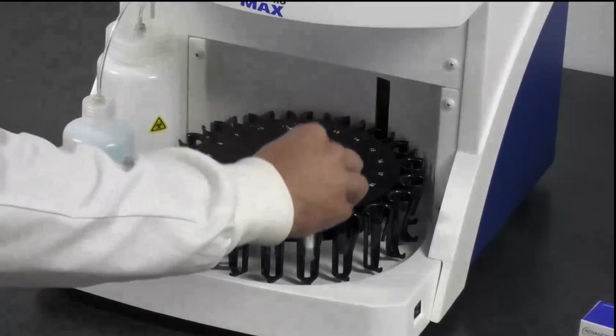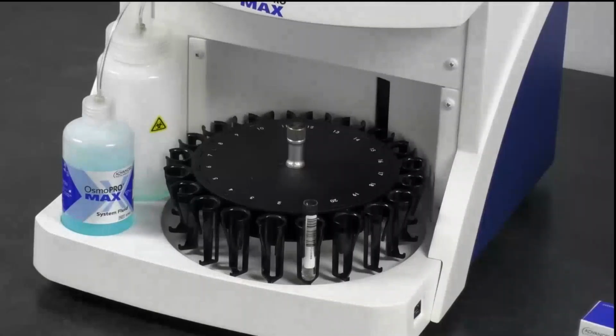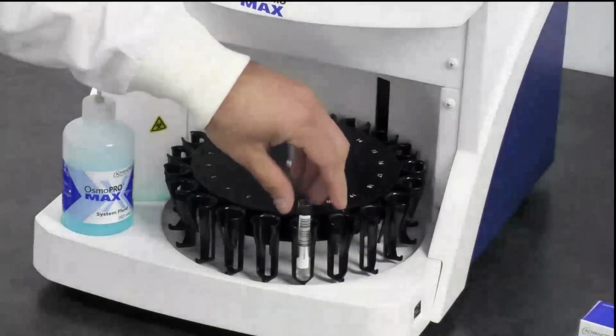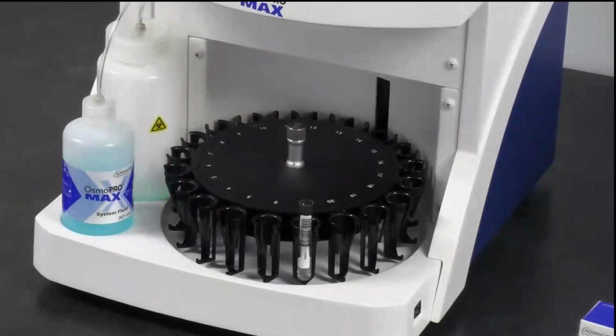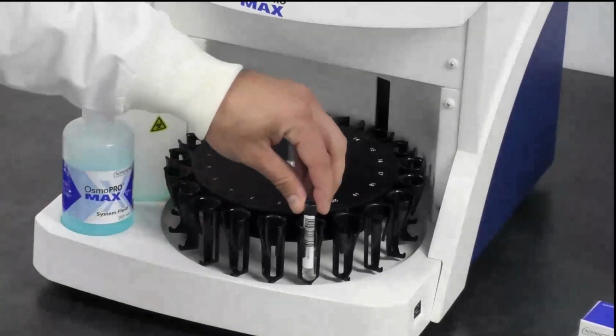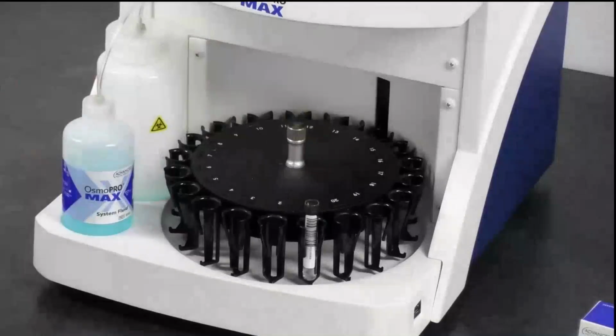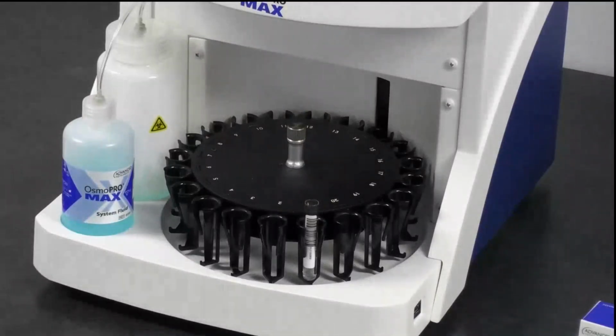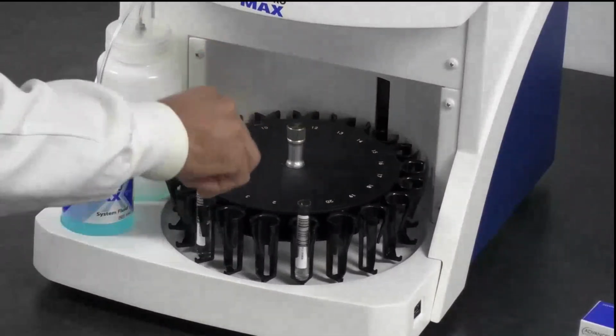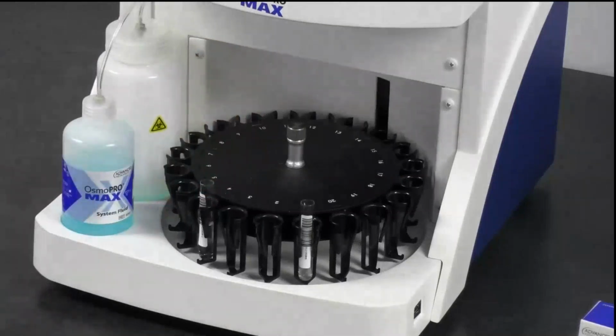So we'll find out. So the first thing you're going to want to do with your primary sample tubes, quote unquote, primary sample tubes. And remember, these are 12 by 75, so they fit on here nicely, just like most tube diameters do, as long as they're under 100 millimeters in height. They're going to fit nicely in this turntable. You just want to make sure that barcode's facing out so that when it does pass by the scanner, it's scanned in. And I'm going to go ahead and put another one here. And remember, we have the instrument pre-programmed to run in duplicate. So for each of these tubes that I'm putting on, it's going to attempt to run 2 tests.